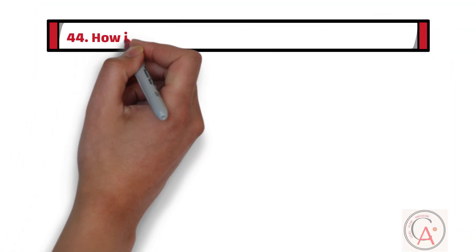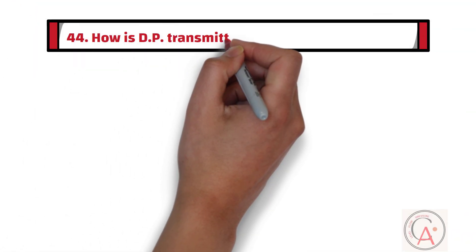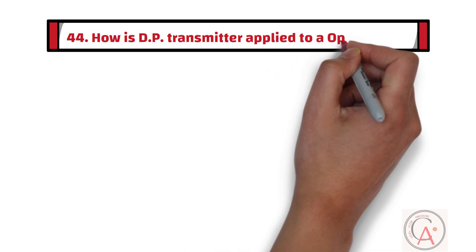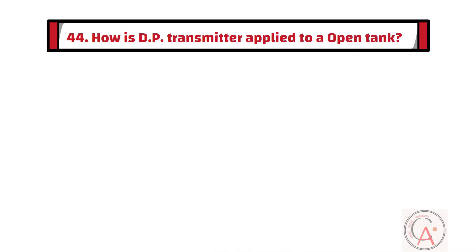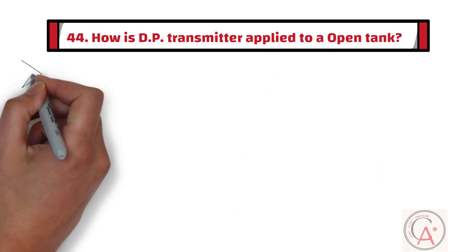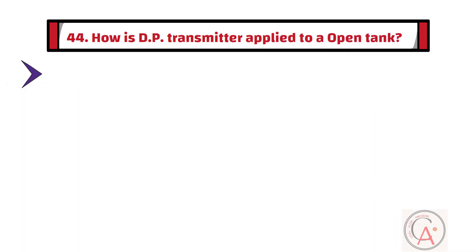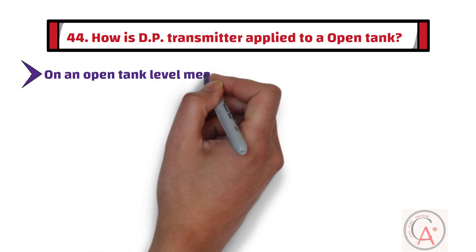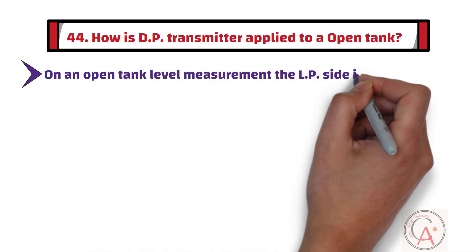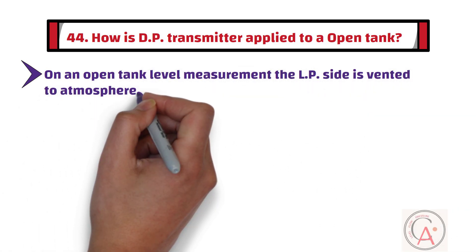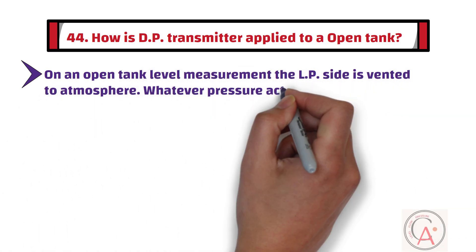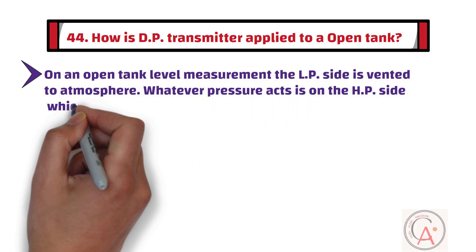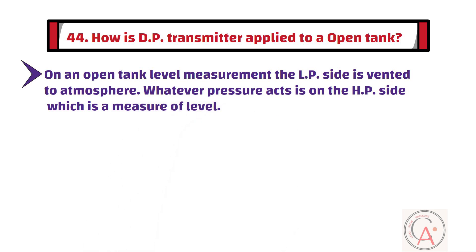Question 44: How is a DP transmitter applied to an open tank? In an open tank level measurement, the LP side is vented to the atmosphere. Whatever pressure acts is on the HP side, which is a measure of level.